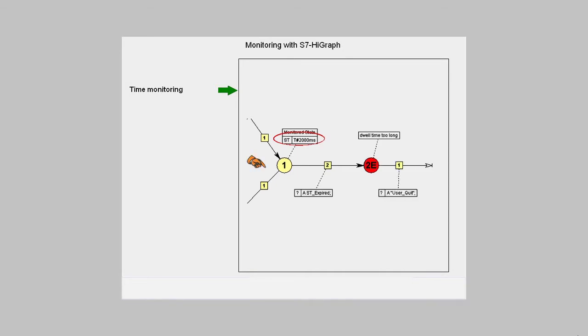Time monitoring indicates whether a transition switches after a fixed time. If after the parameterized monitoring time there is to be branching into a fault state, this is done via a transition with the predefined signal ST expired.